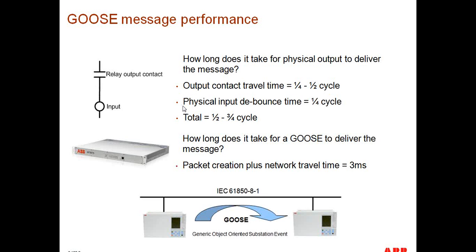Now, substations are a harsh, noisy environment. So to avoid the inadvertent assertion of physical inputs due to induced voltages, due to transients on devices, protective relays have debounce time or filtering times. And that filtering time is usually around a quarter of a cycle. So the total amount of time that it will take one device to realize that that input has actually become a 1 and act upon it is anywhere between half a cycle to 3/4 of a cycle. In the case of a GOOSE message, this is something that is around 3 milliseconds. So as you can see, there are some performance gains utilizing GOOSE messages on that front.